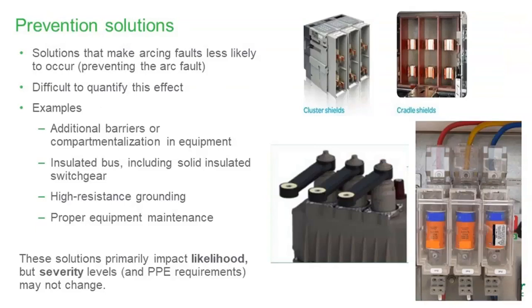So how do we do this? Additional barriers and compartmentalization inside of equipment. You're starting to see equipment with features like those shown in the top couple of pictures. Shields in breaker cradles or on the finger clusters in the back of the breakers make it less likely that you start an arc when you're racking the breaker back into itself, for example.